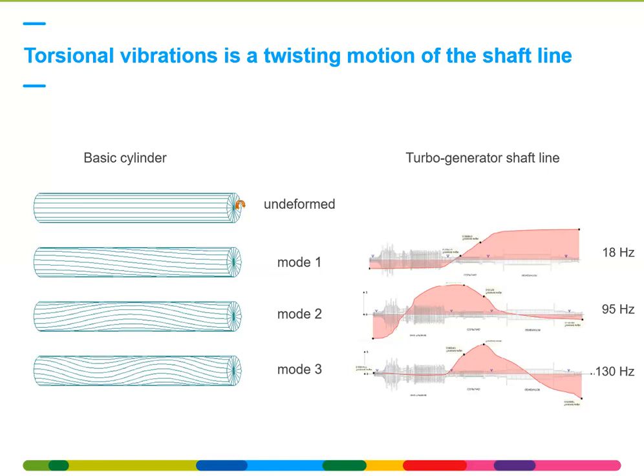The more complex modes are already at much higher frequencies, and these are what they call supersynchronous, so above the grid frequency, and the deformation is also more complex. At 95 Hertz, you can see a deformation already within the gas turbine and the compressor, while the generator is almost doing nothing. At 130 Hertz, it's more the generator mode, while the gas turbine and the compressor are doing nothing. This is in general how the dynamics of the shaft line occur. The lowest natural frequencies start, let's say for steam turbines, around 6 Hertz and go to 20 Hertz. The higher ones, supersynchronous, are typically of less importance. The main important ones are the subsynchronous ones, which will be explained further on.